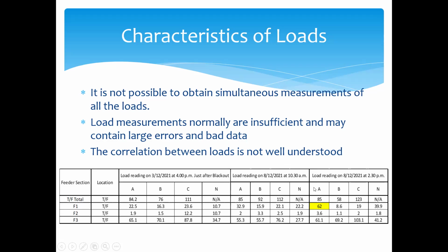For example, if you come to this side, the transformer total current is 85, and when we measure the feeders, in A phase feeder 1 has 62 amp, feeder 2 has 3.6 amp, and feeder 3 has 61.1 amp. So these three should be summed. If you get the summation of these three values, it should be equal to the transformer total. But it's not so. This 62 value may be erroneous, or maybe even it's true.